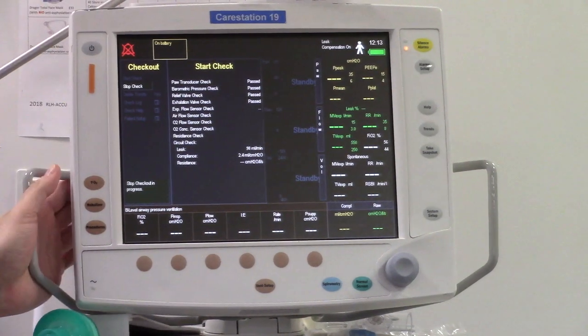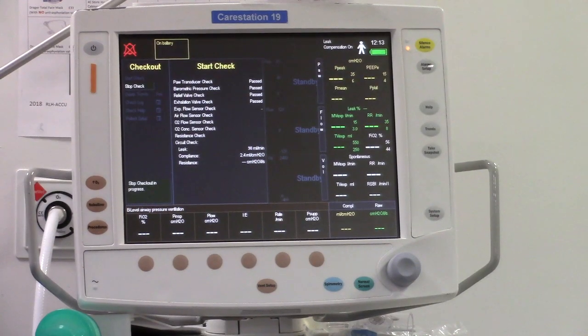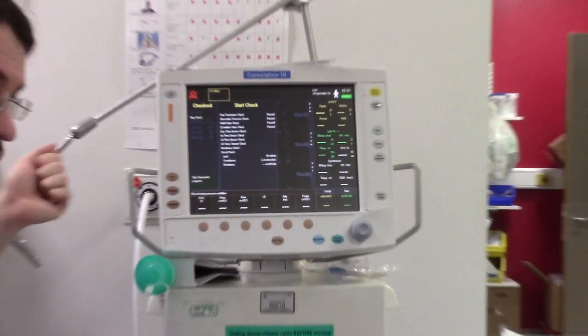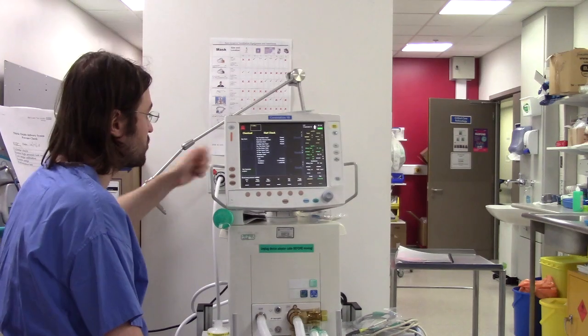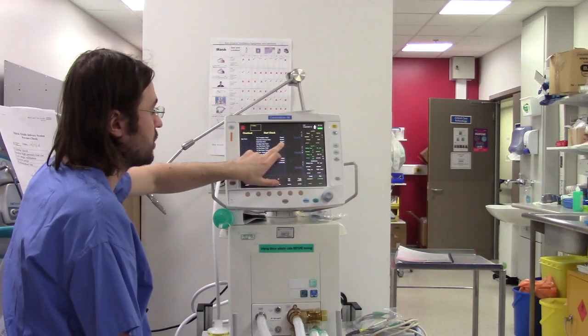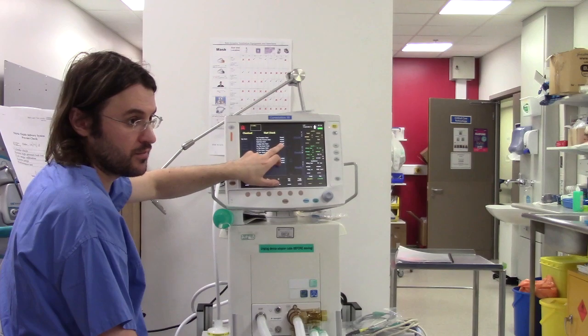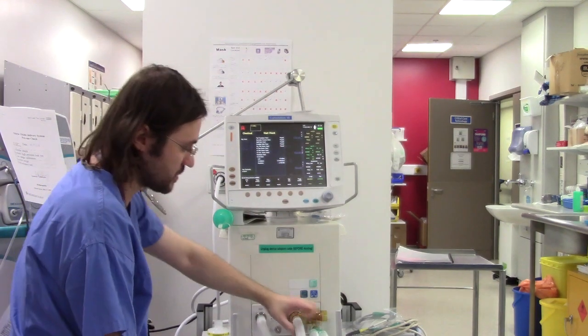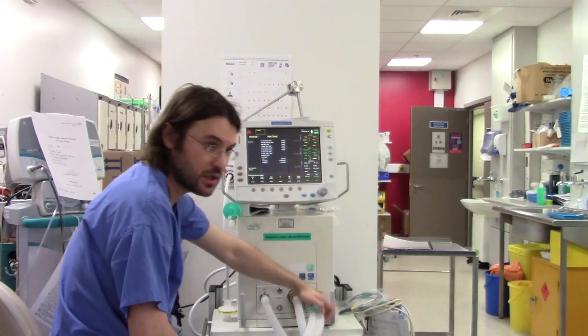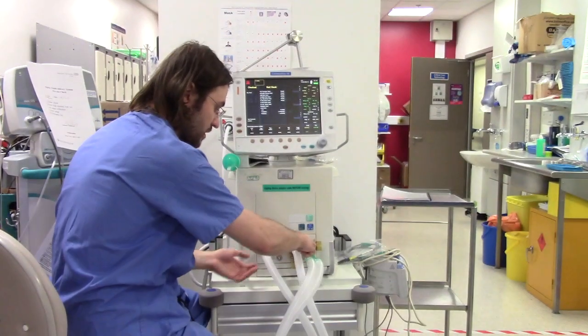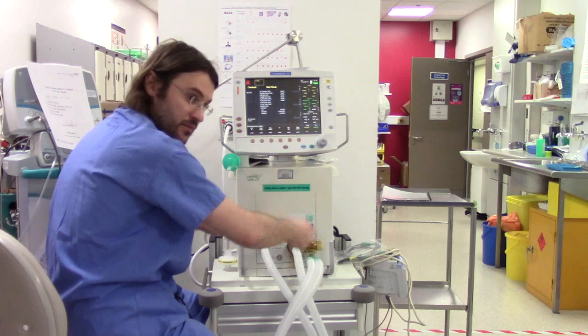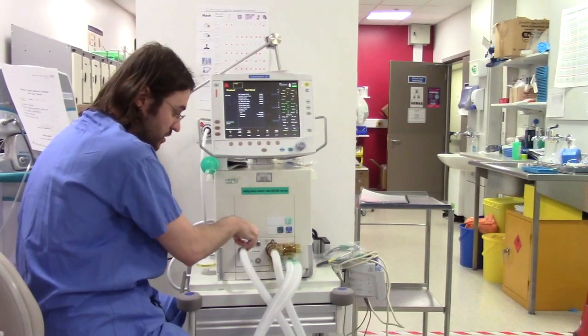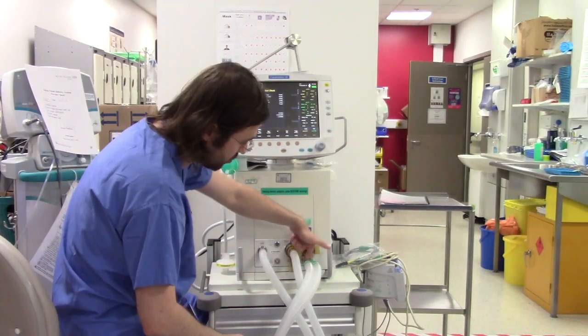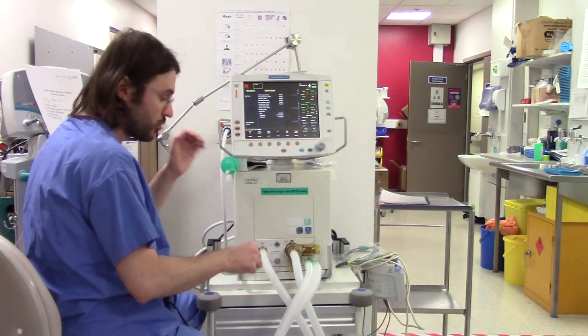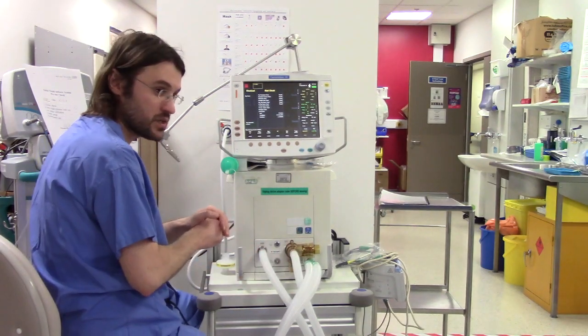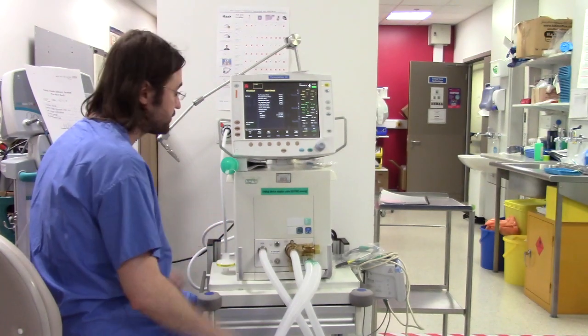And what I mean by the correct steps is you make sure you connect it to the supply. A lot of nurses don't connect it to the supply. They do the previous check, and the first few steps over here will fail straight away. Or the tubings must be connected where they are supposed to be connected. It's simple. This can be connected either here or here. It doesn't matter, as long as one of them is in each port here, and this one is occluded there. Or you can occlude it with the original red cap that comes in the pack of the circuit.